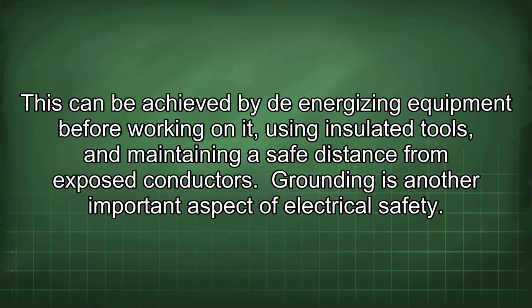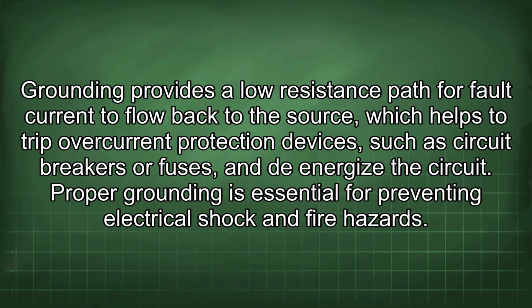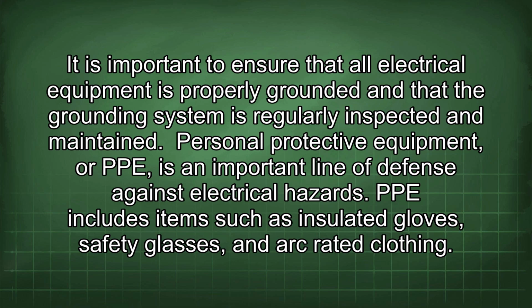exposed conductors. Grounding is another important aspect of electrical safety. Grounding provides a low resistance path for fault current to flow back to the source, which helps to trip overcurrent protection devices, such as circuit breakers or fuses, and de-energize the circuit. Proper grounding is essential for preventing electrical shock and fire hazards. It is important to ensure that all electrical equipment is properly grounded and that the grounding system is regularly inspected and maintained. Personal protective equipment, or PPE, is an important line of defense against electrical hazards.